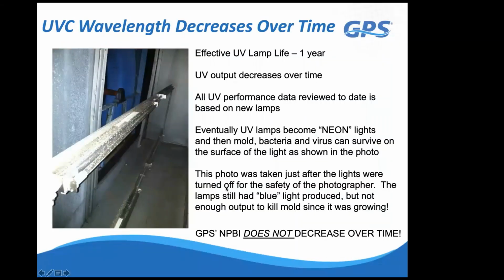If you are using UV lights, or any other technology that does require maintenance, make sure you're doing the maintenance on it. Here's a picture of a UV light that was sent to me from a prominent hospital down in Texas, and they actually have mold growing on the UV light. Now, I was told that when this picture was taken, right before they opened the door to the air handler and the door switch killed the light, it was still glowing blue.